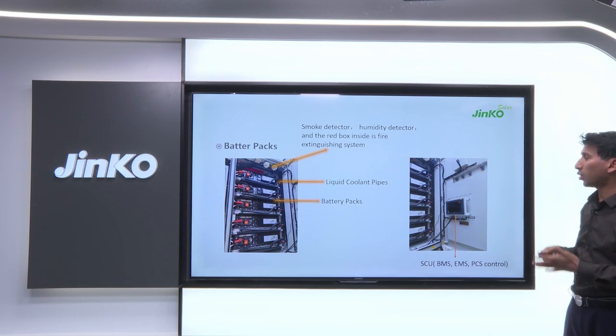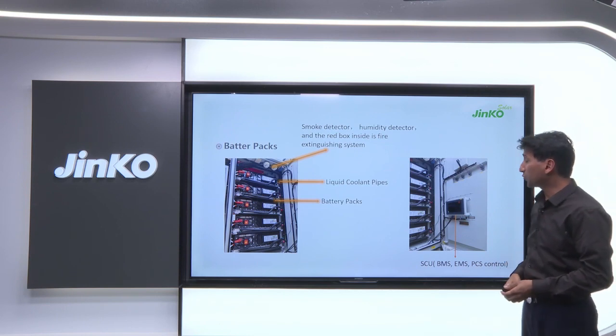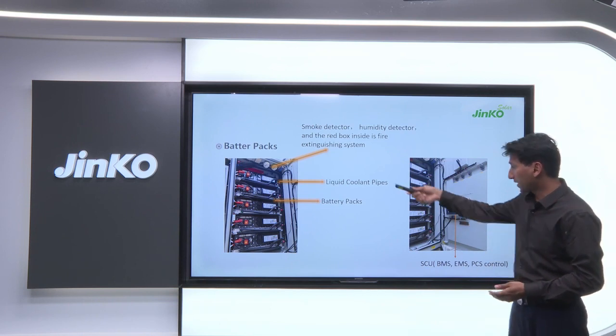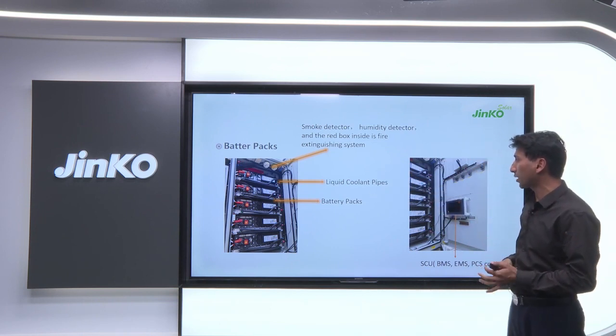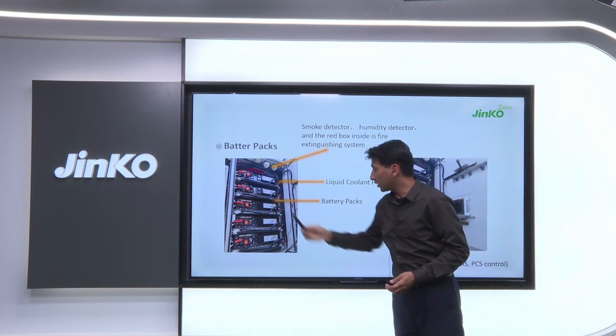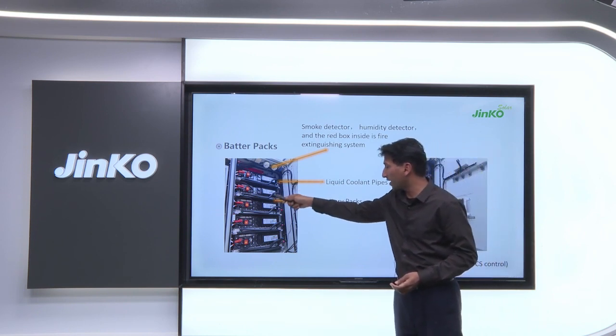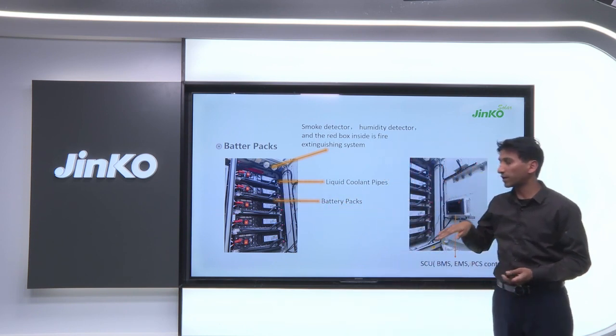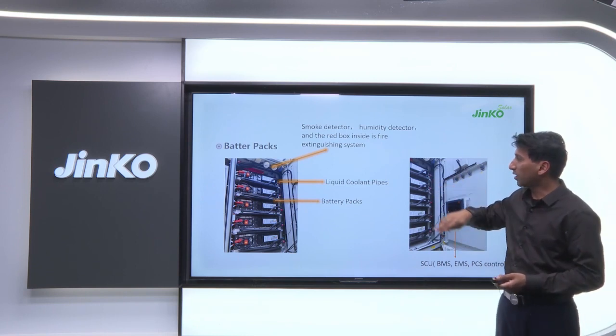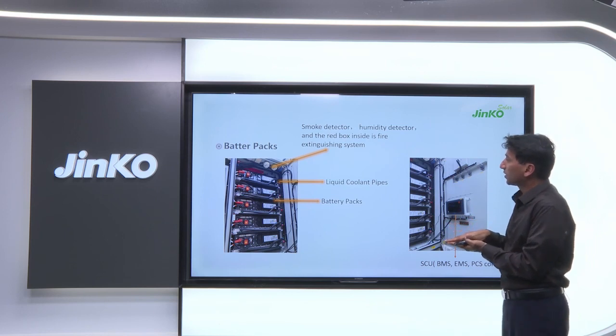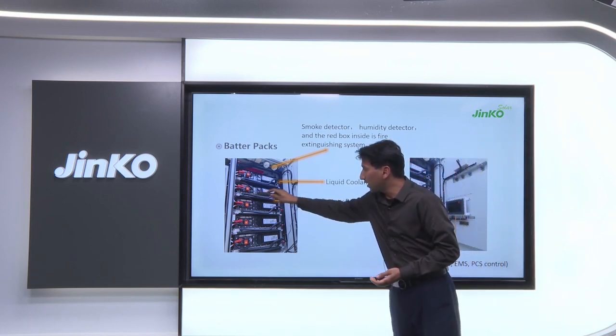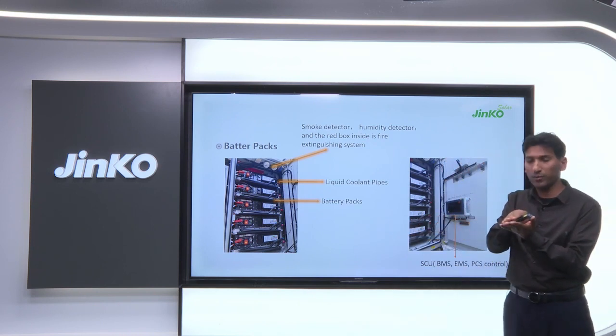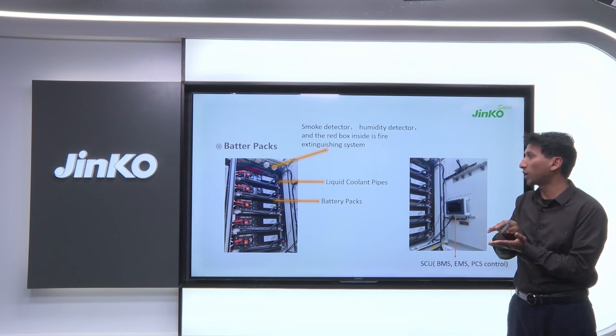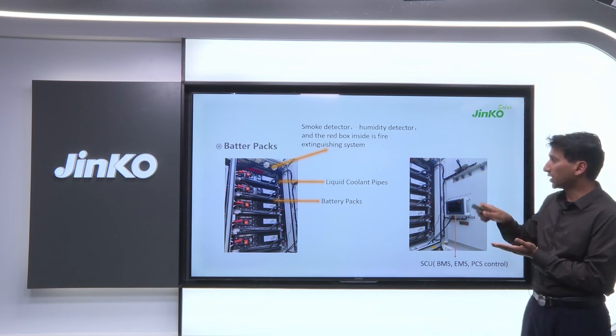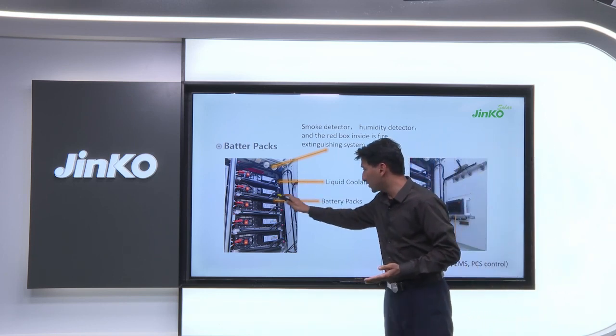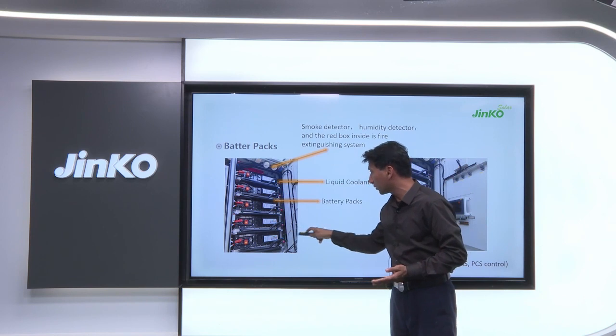We are now discussing all the parts one by one. Moving to the first one, the battery packs. As you can see in the picture, all the power cables are already very well connected, and all the communication cables are already connected too. These pipes are used for taking the liquid from the liquid unit into the plate. All these batteries are placed on this metal plate. The plate is hollow inside, and the liquid that cools the batteries, keeping them at normal temperature, comes in from these pipes, goes inside, comes out through the other pipe, and keeps moving between all the battery packs.